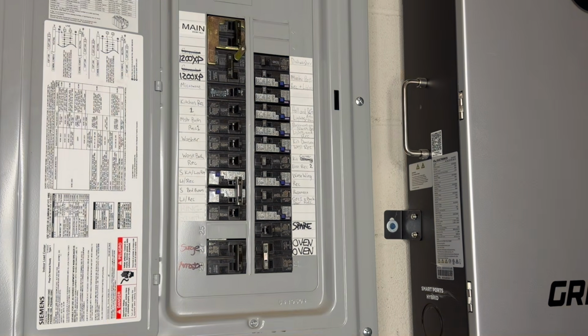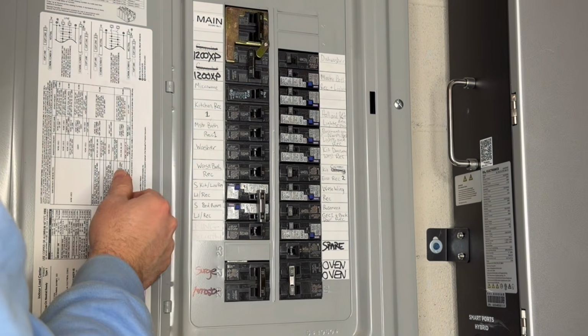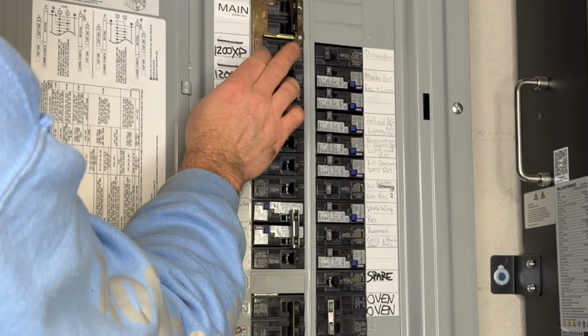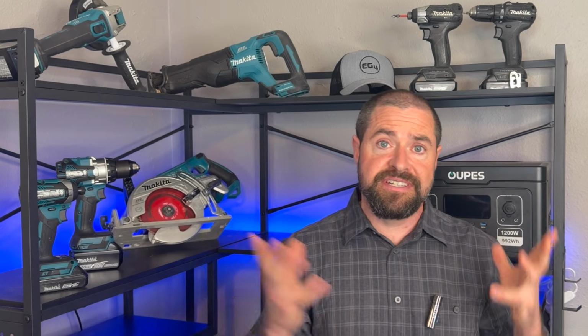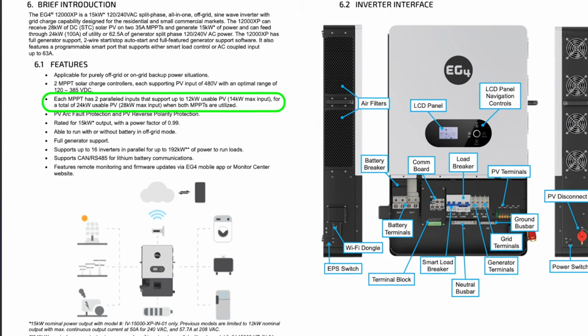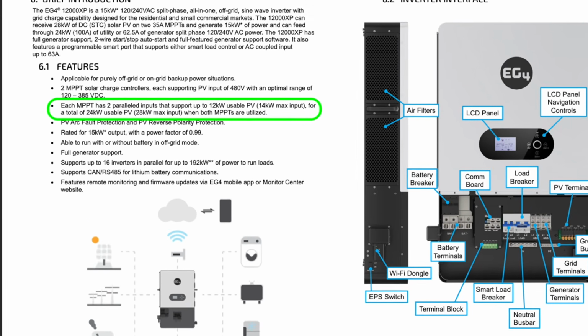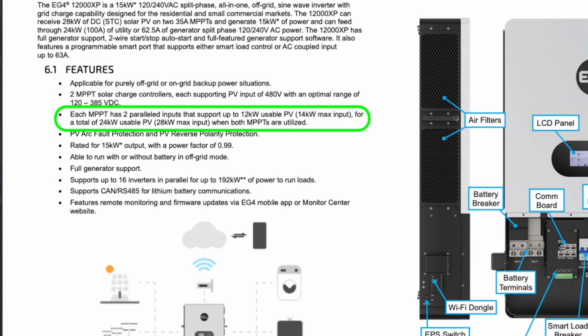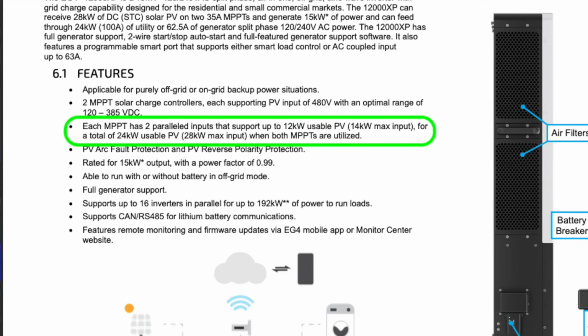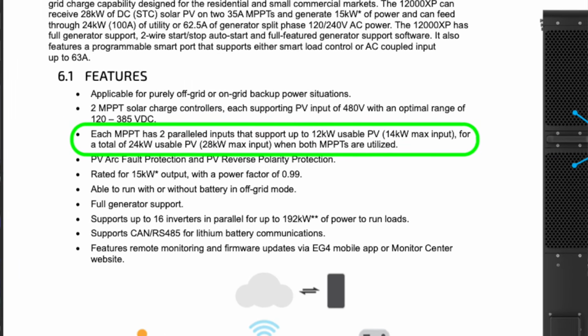Although most households run on a 200 amp service, you can really cram a lot of loads into a 100 amp critical loads panel. It accepts up to 24,000 watts of solar panels into the DC inputs. That's up to 12,000 watts per maximum power point tracker. So you can have two separate arrays facing different directions or in different conditions, both bringing up to 12,000 watts down into those maximum power point trackers into your solar DC inputs.